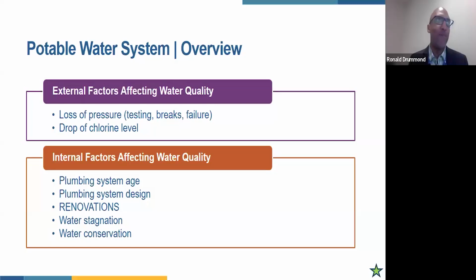Internally, lots of factors affect the quality of your water. These include plumbing system age, so materials for construction and state of the infrastructure. The initial design and subsequent renovations, Jessica talked about this, a shower that gets turned into a library. That's not something we typically plan on when we engineer and design a system. Other things that can happen over time or at the initial development of the building are cross connections. So these are systems that are connected improperly, either at original construction or during renovations. We also have dead legs. We have check valves that may have failed over time, and it leads to that bleeding of water between one side and another. As mentioned before, water stagnation is a major concern. We try to alleviate that.